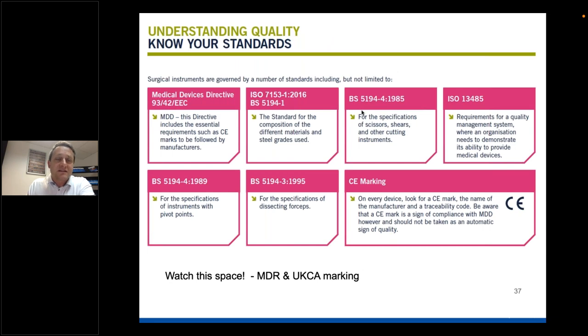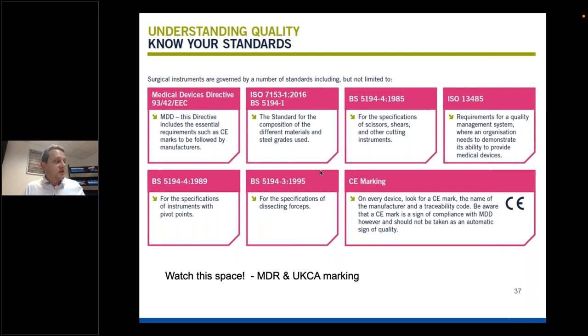There is some steel and forges produced in Germany and Europe, but volumes are much lower than the big producers. The key point is understanding the standards we must meet regardless of where the steel is manufactured. For surgical instrument manufacture, ISO 7153-1 is the important standard - though it has been updated since 2016. This gives compositions for every instrument and specifies what types of steel should be used. If you don't follow that, you're unlikely to produce an instrument that's fit for purpose.